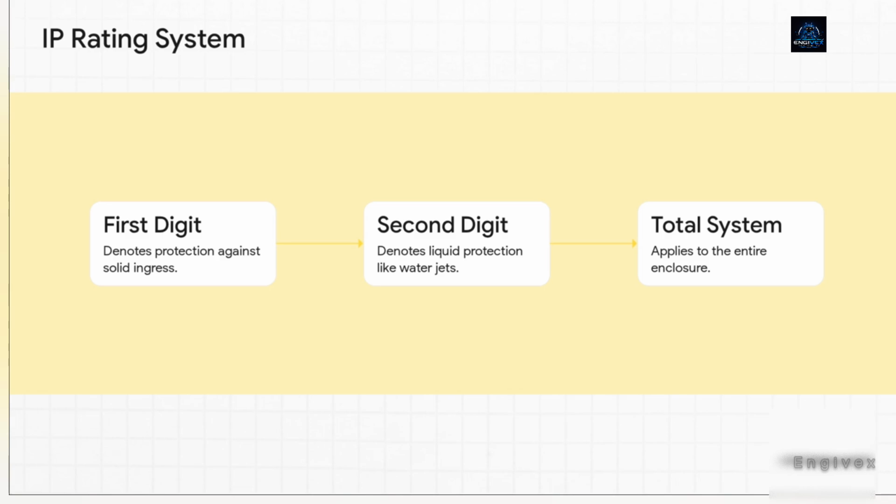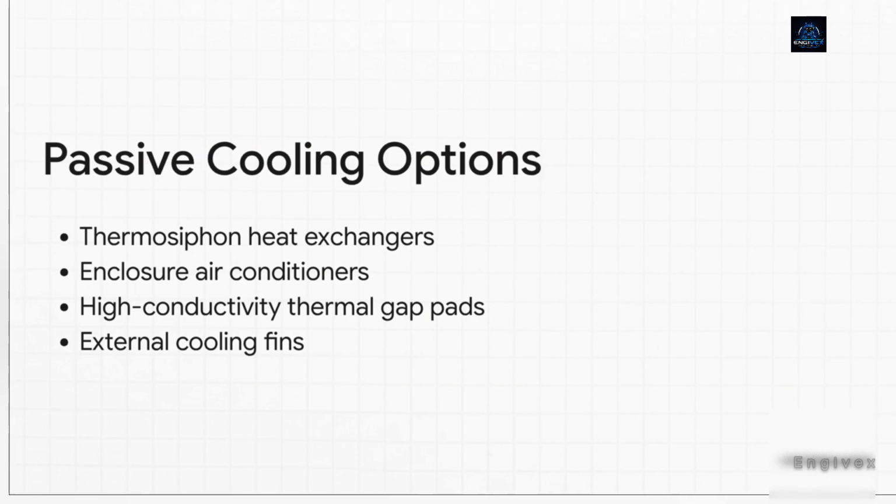For context, the 6 in IP65 means it is fully dust-tight even under vacuum testing, and the 7 in IP67 means it can survive temporary submersion in water up to a meter deep. To pull that off, the entire housing, the sheet metal tolerances, the structural stiffness, the silicone gasket compression has to be perfectly co-optimized. Cutting a giant fan hole on the side, yeah, simply not an option. For these tightly sealed systems, your thermal design has to pivot completely to conduction. You're using metal standoffs, thermal gap pads, or closed-loop air conditioners. Basically, you have to route the internal heat directly into the enclosure walls.